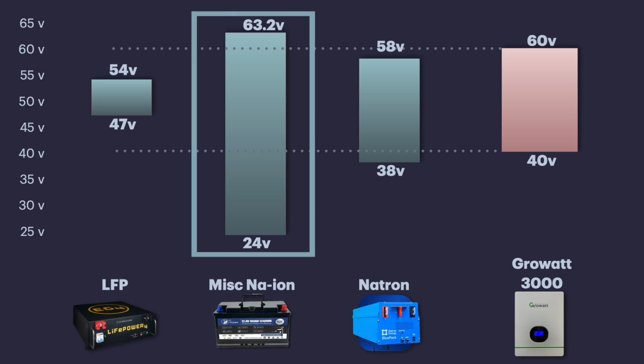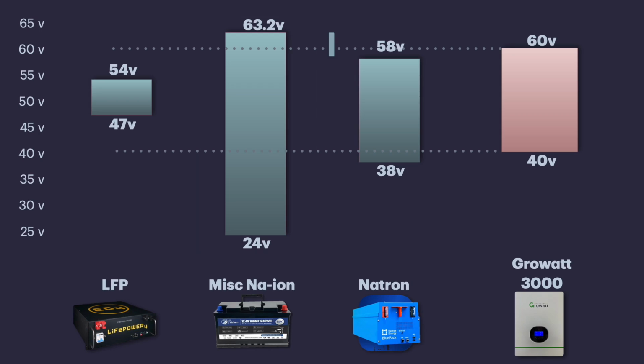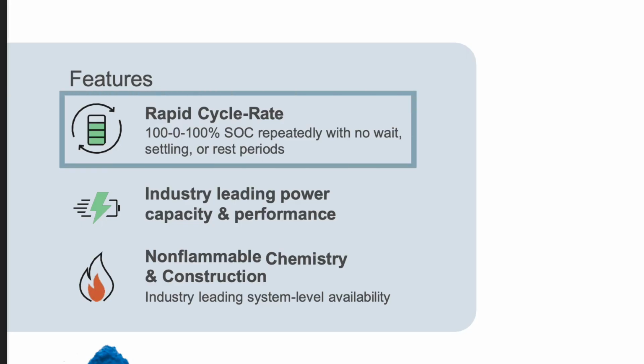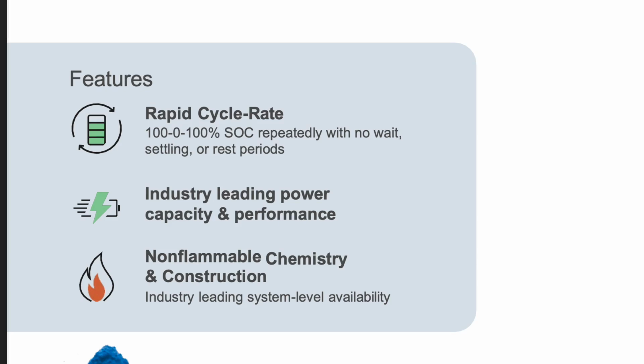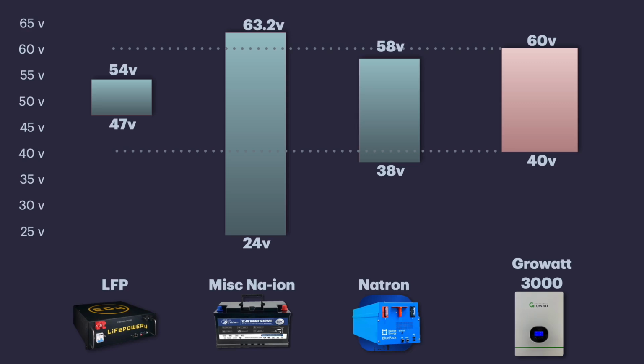Over on these miscellaneous sodium ion batteries, without actually testing them in the real world, I don't know how accurate this high to low range even is or how usable it is. Meanwhile, Natron claims you can use their battery from 0% state of charge all the way up to 100% state of charge, so in that aspect Natron has a clear advantage over the other batteries. The wider voltage range of the sodium batteries isn't really a clear-cut advantage over the smaller voltage range of the lithium iron phosphate; it just means the voltage drops faster in the sodium chemistry.